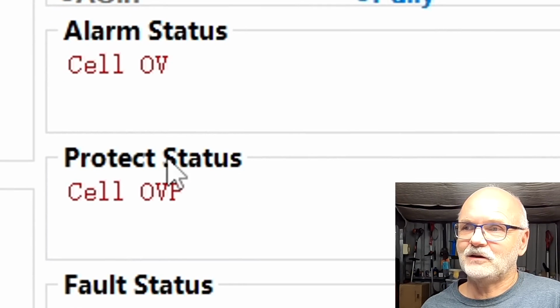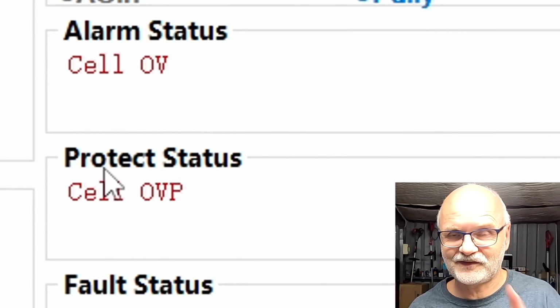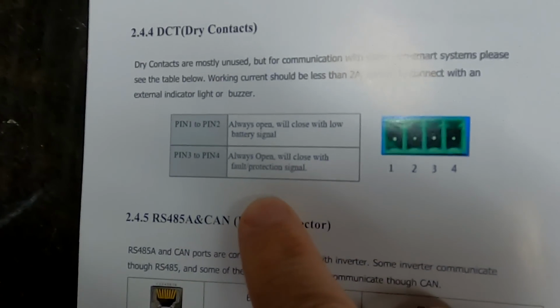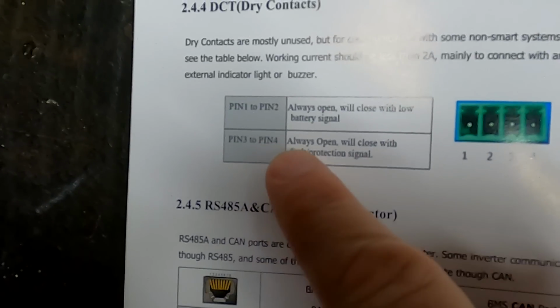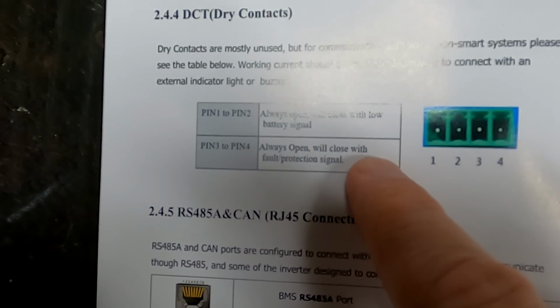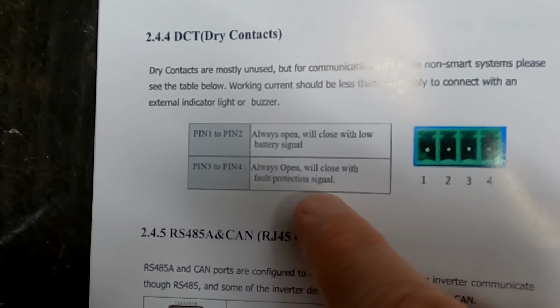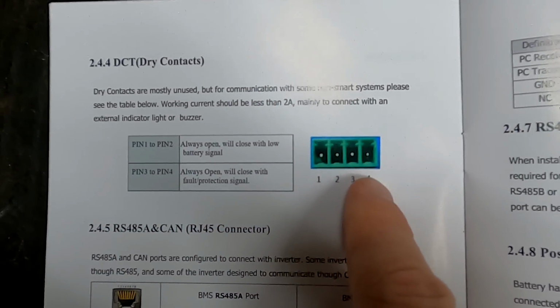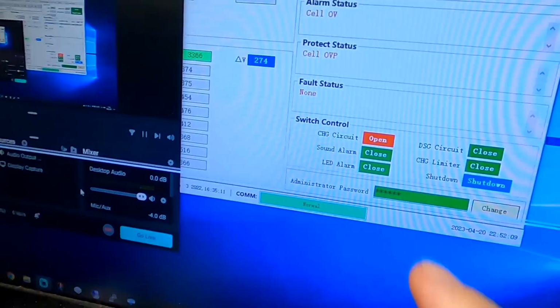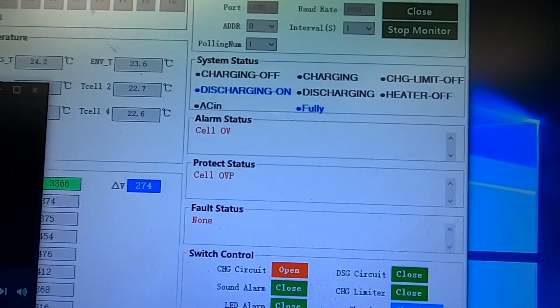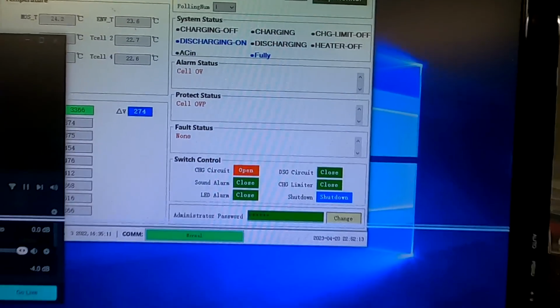It says now the battery is full. We've got a protection status, we've got an alarm status. Let's measure the relay again. So just as a reminder, it says here pin 3 and 4 always open, will close with fault or protection signal. So this is 3 and 4 on this side. And we clearly have an alarm and protection status at the moment.